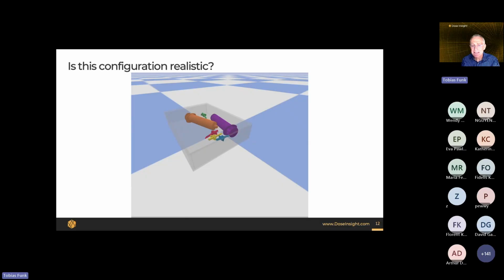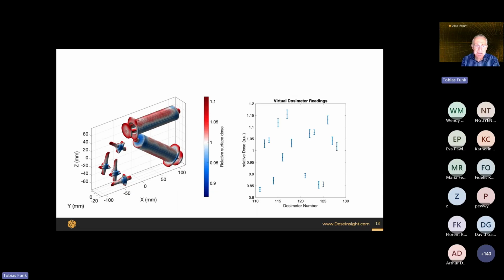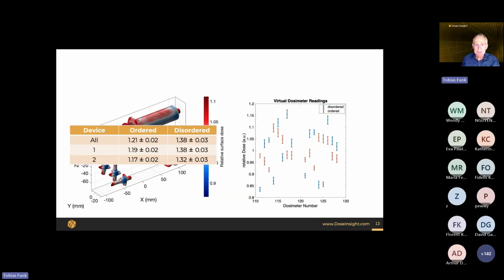So rather than being nicely ordered, as we saw before, we have now quite a bit of disarray in the box. And let's see what it does for our virtual dose mapping if we take that into account. So this is our unordered or disordered medical device, and we again do virtual dose mapping, and we can compare that now to our ordered device, and we see the dose is really spread out much more than before, and our dose uniformity ratio goes up from 1.21 to 1.38, so significantly higher.